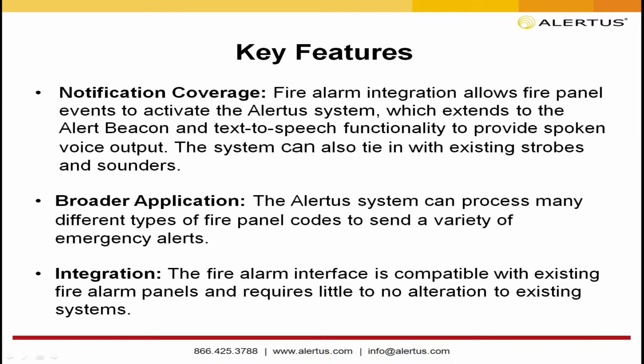Thanks, Rodrigo. Absolutely. Yeah, I bring that up because I was actually out at a DoD facility that had an incident. They did a risk analysis and found out that their strobes are labeled fire. They don't want to use those in that kind of an incident. So they actually went through and relabeled them so that they could also turn those on. Now they would mute the announcement that said fire if it was a mass notification, and then they would use another means for announcing what the actual emergency is. But they actually went through and relabeled every one of them so that they could use those in an event of emergency.